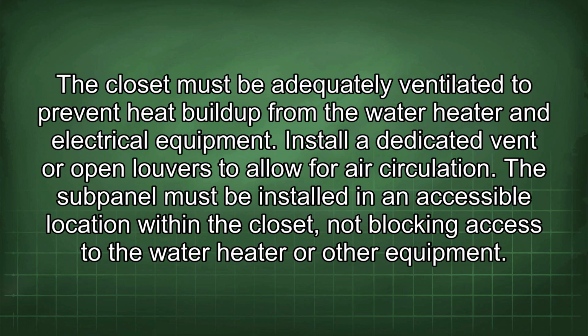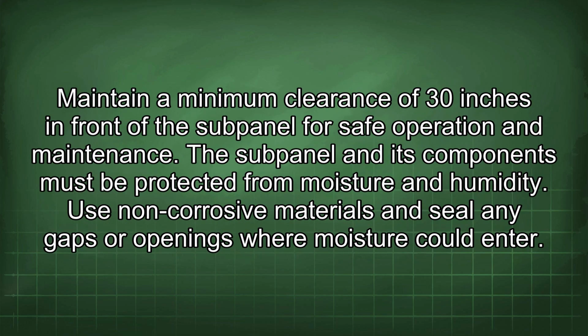The closet must be adequately ventilated to prevent heat buildup from the water heater and electrical equipment. Install a dedicated vent or open louvers to allow for air circulation. The subpanel must be installed in an accessible location within the closet, not blocking access to the water heater or other equipment. Maintain a minimum clearance of 30 inches in front of the subpanel for safe operation and maintenance.